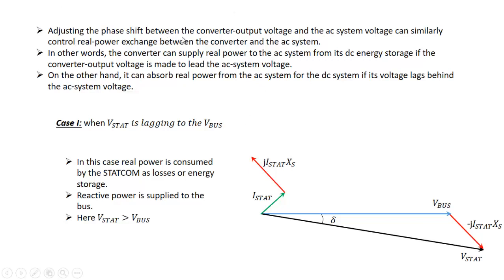By adjusting the phase shift between the converter output voltage (V_STATCOM) and the AC system voltage, we can control real power exchange between the converter and AC system. The converter can supply real power to the system from its DC energy storage if V_STATCOM leads V_bus. Conversely, if V_STATCOM lags V_bus, the converter can consume real power — to compensate for its own losses, or to charge an energy storage device.